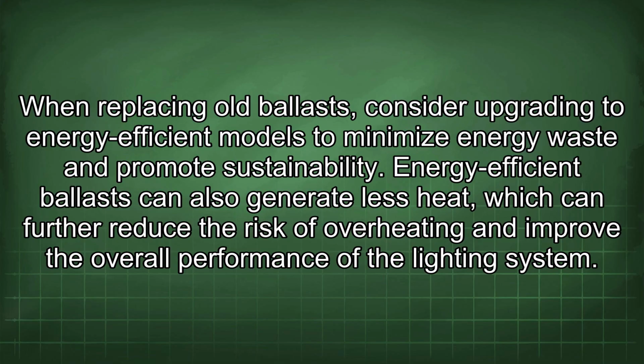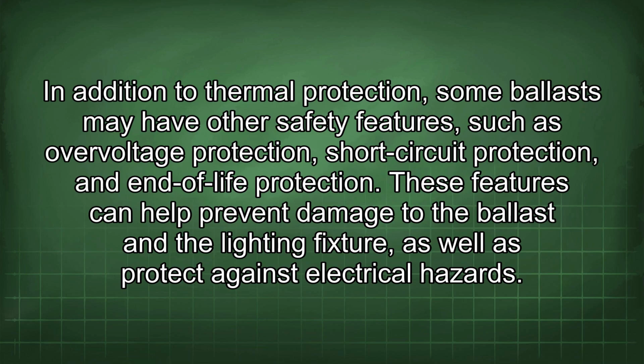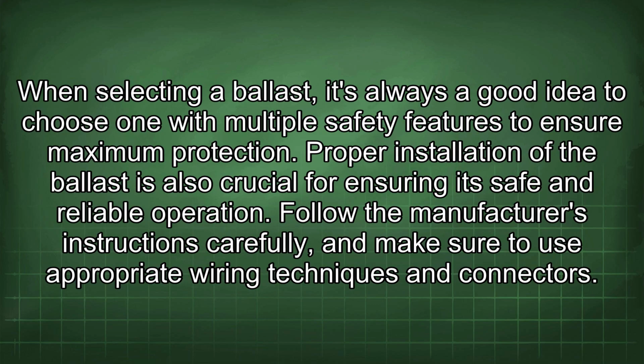In addition to thermal protection, some ballasts may have other safety features, such as overvoltage protection, short-circuit protection, and end-of-life protection. These features can help prevent damage to the ballast and the lighting fixture, as well as protect against electrical hazards. When selecting a ballast, it's always a good idea to choose one with multiple safety features to ensure maximum protection.